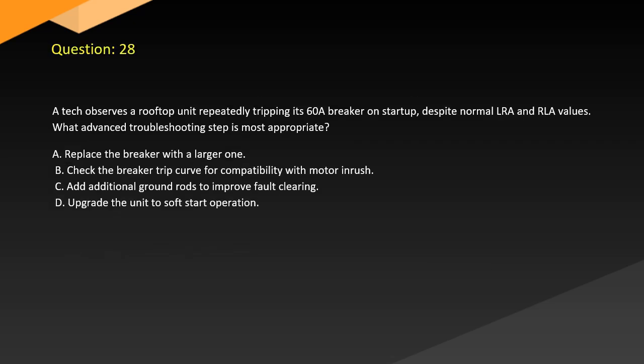Question 28. A tech observes a rooftop unit repeatedly tripping its 60-amp breaker on startup despite normal LRA and RLA values. What advanced troubleshooting step is most appropriate? A. Replace the breaker with a larger one. B. Check the breaker trip curve for compatibility with motor inrush. C. Add additional ground rods to improve fault clearing. D. Upgrade the unit to soft start operation.